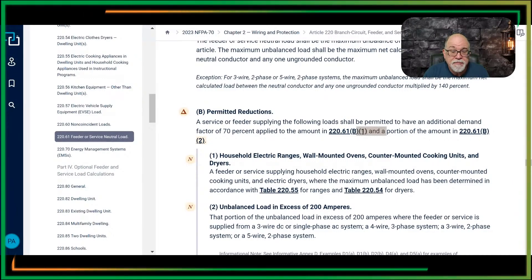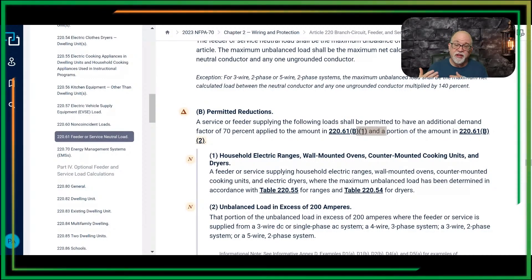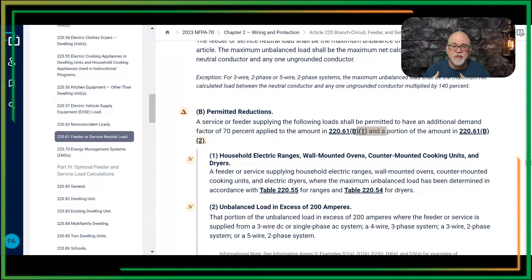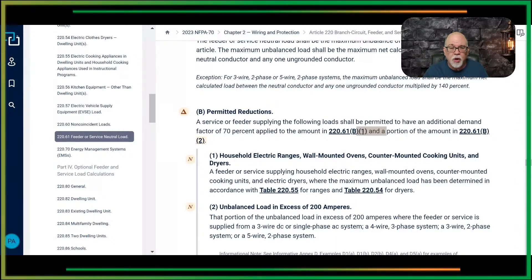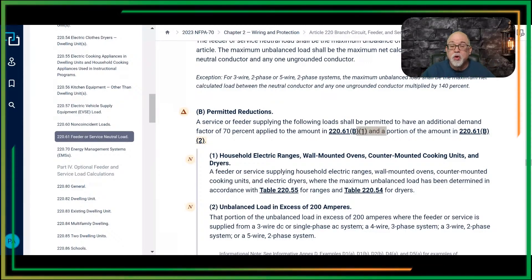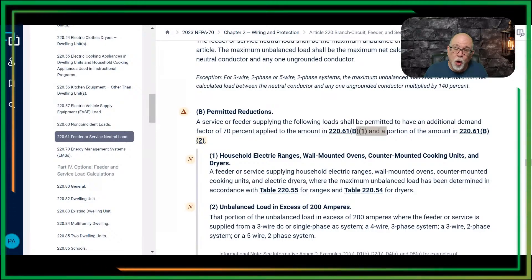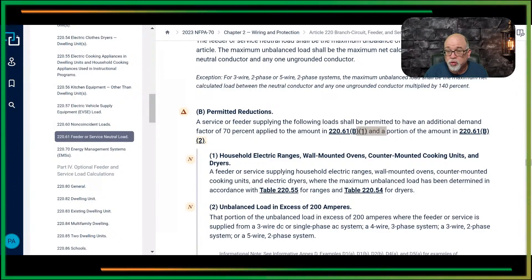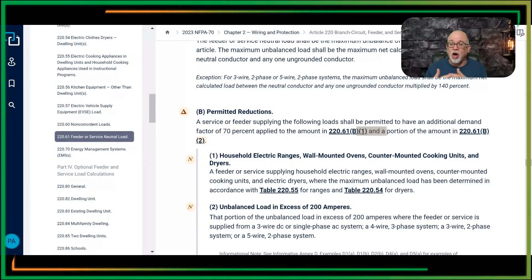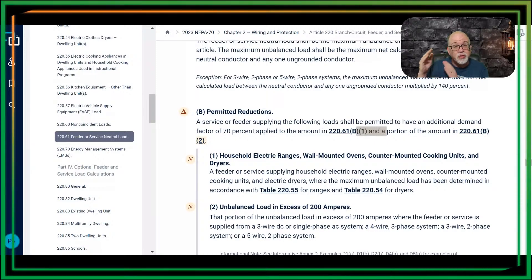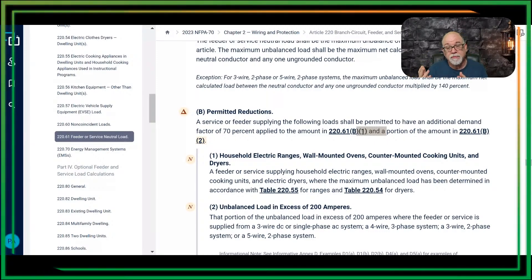...it says you can apply the 70% for the neutral for the ranges, wall-mounted ovens, counter-mounted cooking units, and clothes dryers. You can apply the 70%. But if you still have over 200 amps of neutral contribution, you can also apply the 70% to the portion that exceeds 200 amps as well.